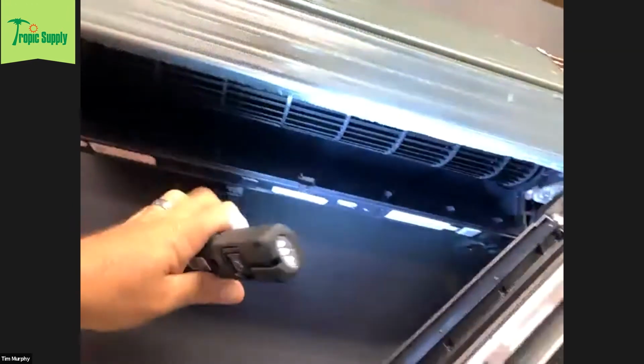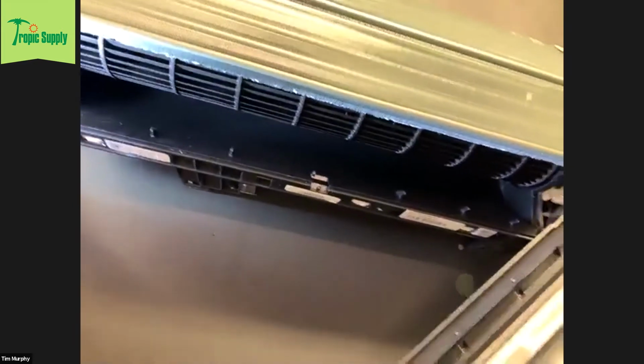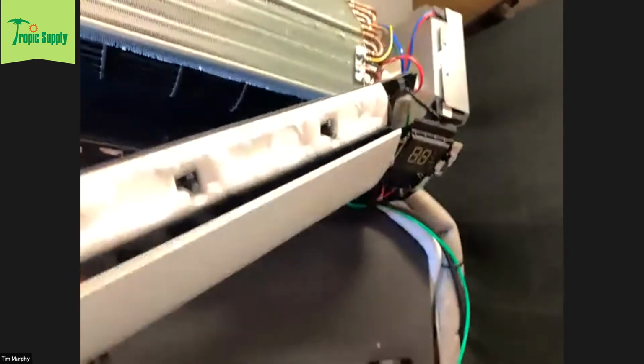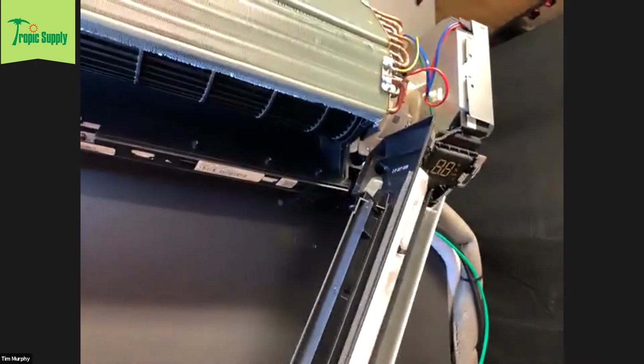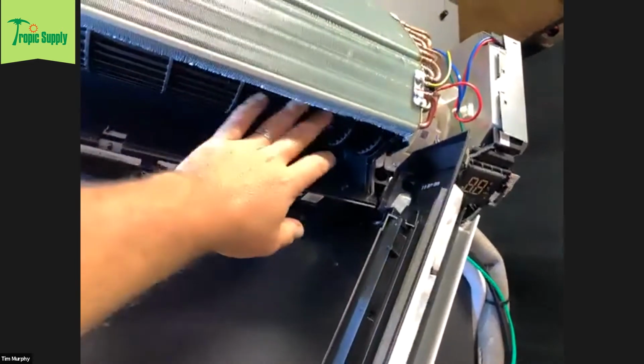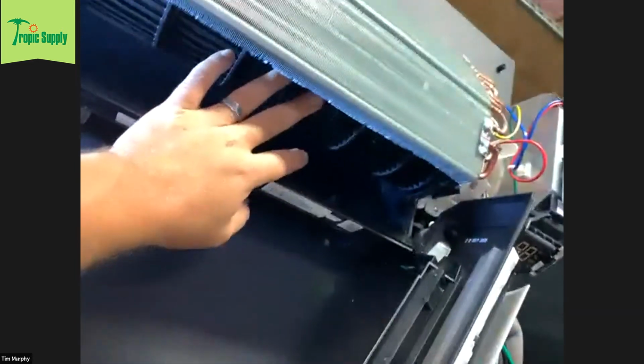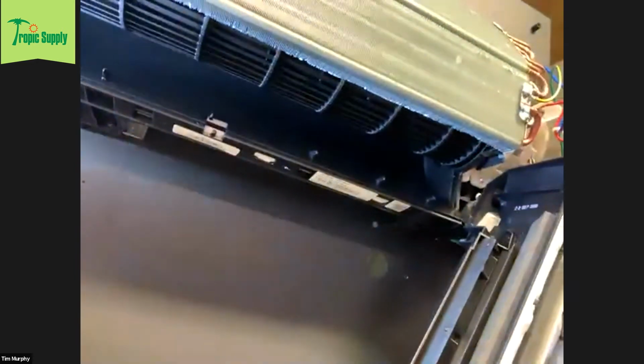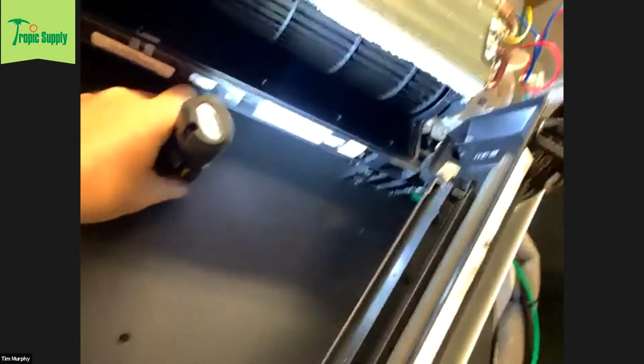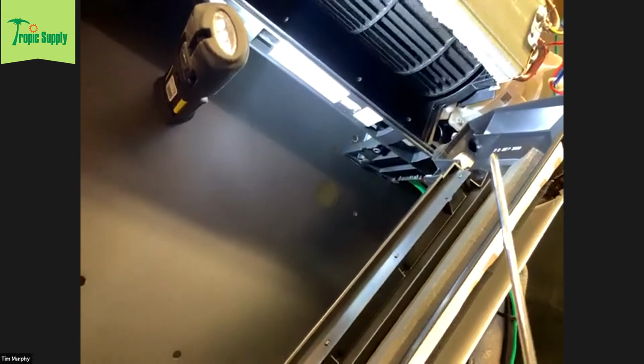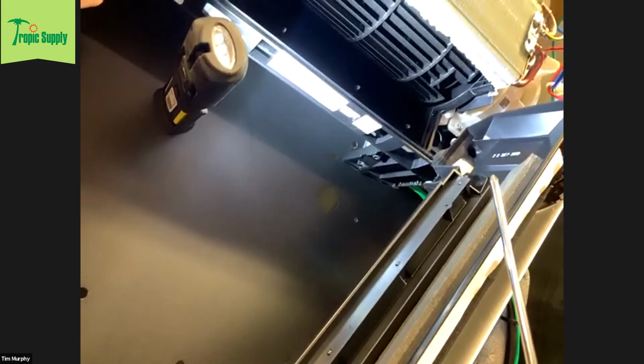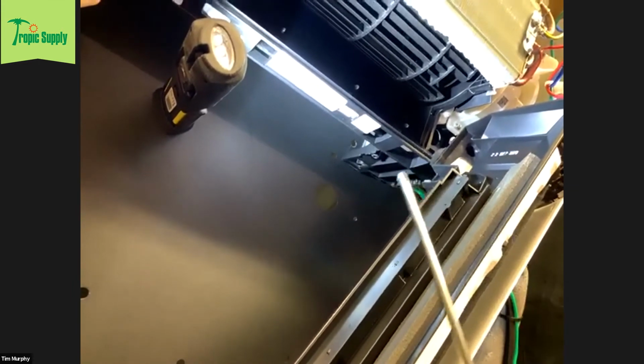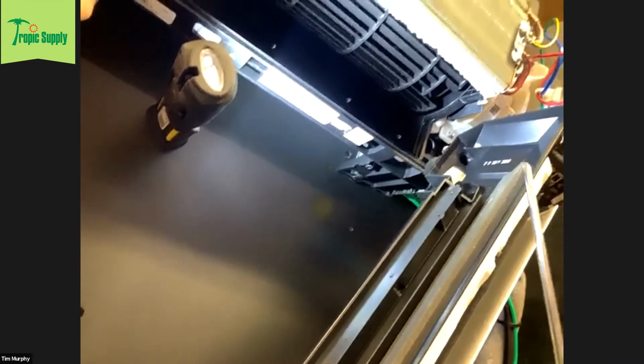The issue I have with that is you'll get water onto the blower shaft. It's pretty tight in here, so you can't get a puller in later. That water sits in there and can cause it to seize onto the blower, so if you need to remove it in the future, you won't be able to.